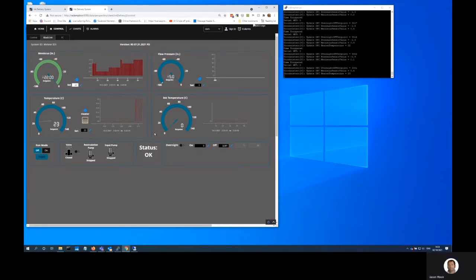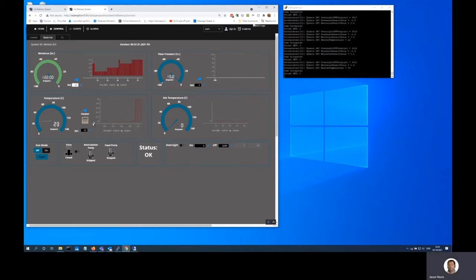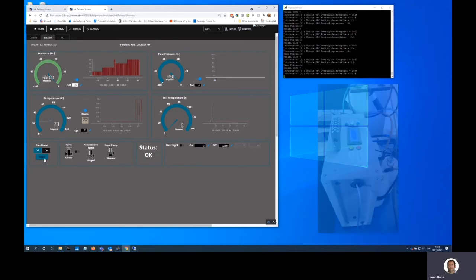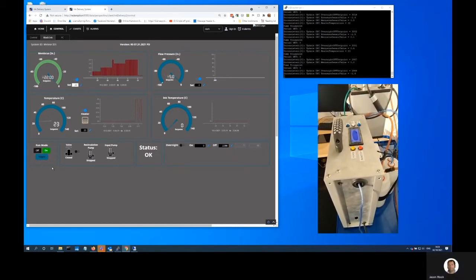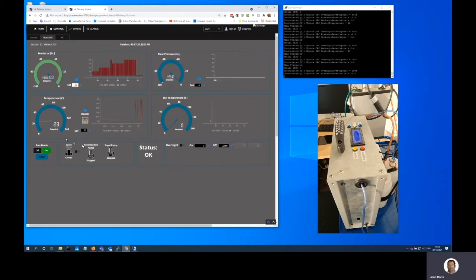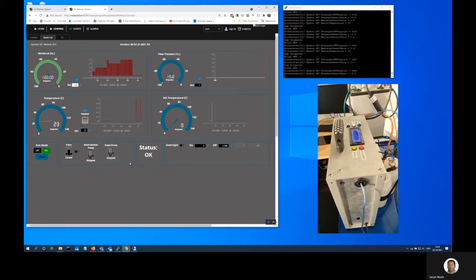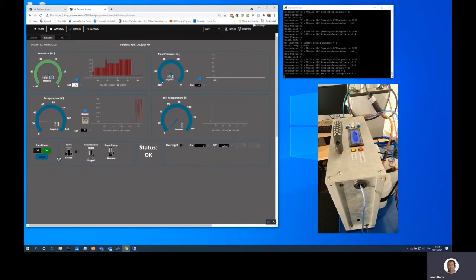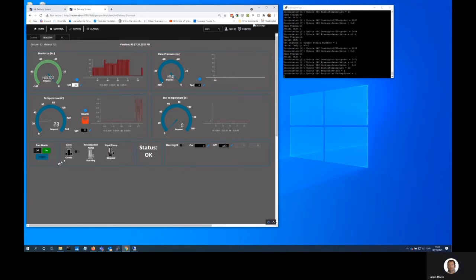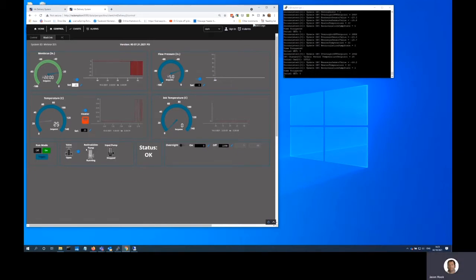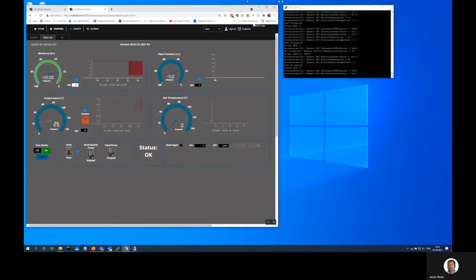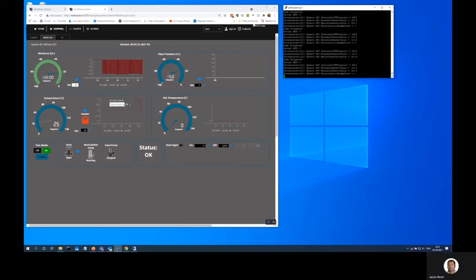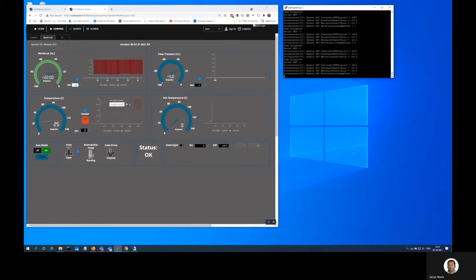We have bi-directional communication between the SCADA application and the ink delivery system, which is going to allow us to turn the machine on. And we get feedback directly to that because the button has gone from off to on and to green. We can turn the valve on. The heater is turned on automatically because it's detected that the ink temperature is low. We can ask the heater to produce more heat. And that will write a value to the OPC UA server. And the OPC UA server will in turn, over the serial interface, tell the ink delivery system what it needs to do. So there's the SCADA application working in real time, giving us immediate feedback about what's happening to the delivery system across the internet.